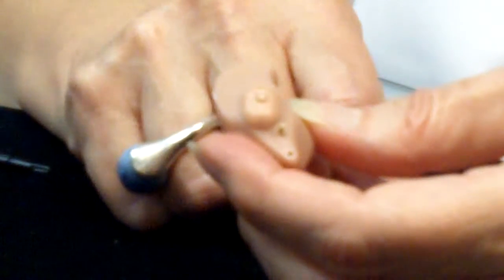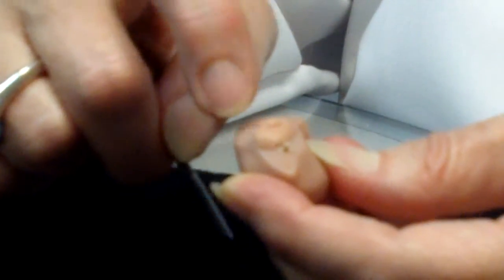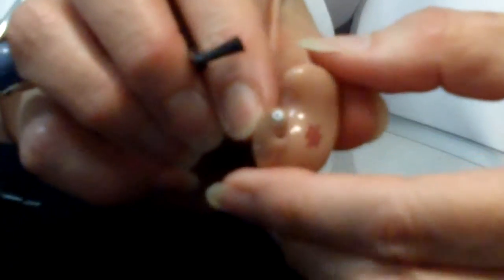These two little ports right here are the microphones. You can see they're very tiny. It doesn't take a lot of dead skin or oil to clog those up. So at night, before you put this one to bed, take your brush and brush across both of those microphones. You may not think you're doing anything when you brush, but dead skin's invisible. We shed a lot of it all the time, and we don't want the dead skin and oil to get down inside the microphone diaphragm and cause the microphone to fail. So brush.